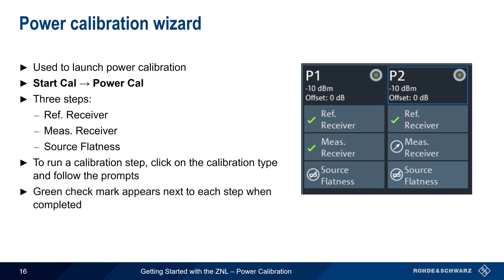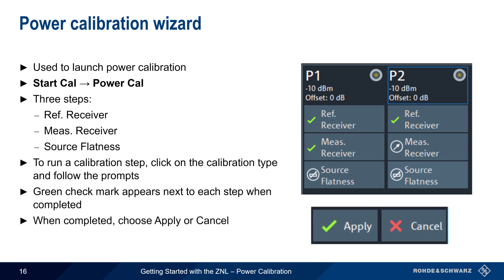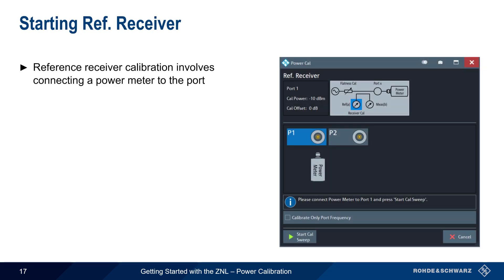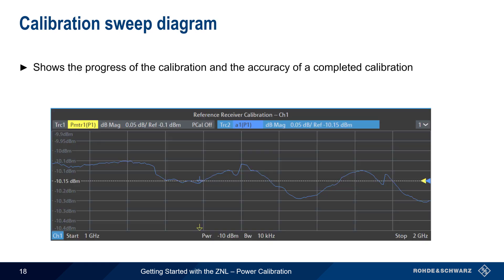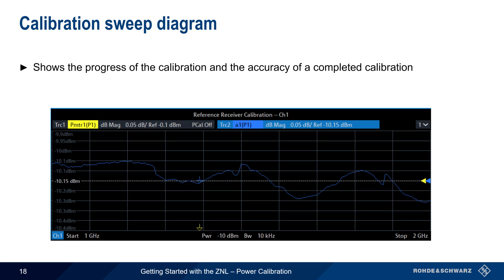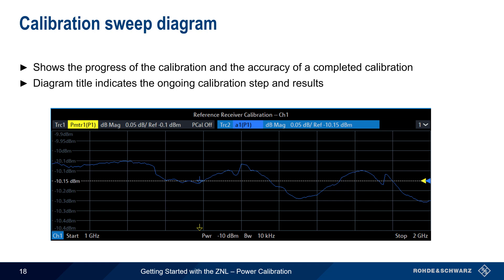Reference receiver calibration involves connecting a power meter to the port being calibrated — generally a Rohde & Schwarz NRP Series RF power sensor. Once the sensor is connected, simply press Start Cal Sweep to run the calibration, which only takes a few seconds to complete. At the top of the power calibration window, a calibration sweep diagram shows the progress and accuracy of the completed calibration. These diagrams are also available for other steps, and the title of each diagram indicates the current calibration step and the measured calibration results.